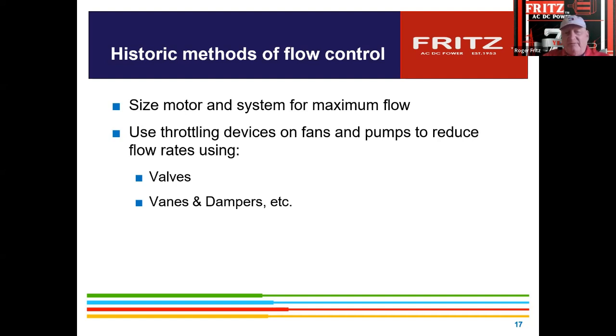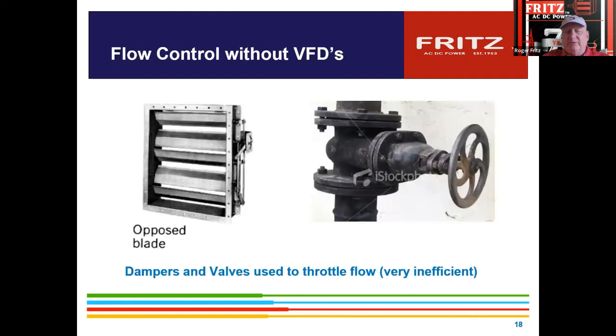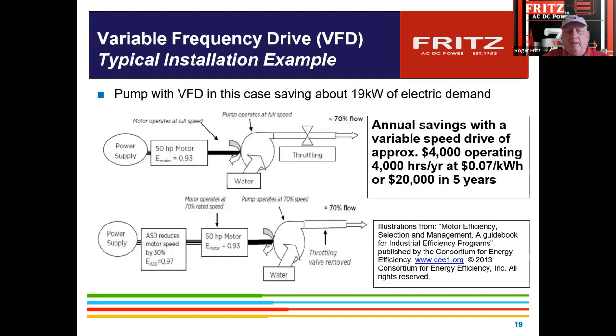So they were controlling it by vanes and dampers. That's the typical thing in a building, regulation valves. So this was the typical way of throttling the output of a water pump, where now they open up the valving, and then they control it with a VFD on a 50 horsepower motor. So it does have a very big impact on total power requirement.